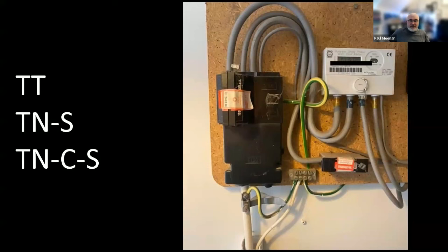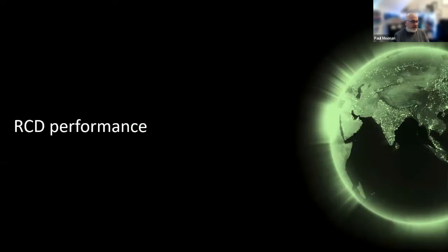We have TT, Terra Terra, which is earth electrodes, if you only have a supply live and neutral. We have TN-S, Terra Neutral Separate, so it comes in completely separate. And then TN-C-S, Terra Neutral Combined Separate, which is that cable there. It comes in from the bottom and basically connects into the fuse. But as you can see, that's a hybrid arrangement. In fact, if you look at the white cable in the earth terminal, that could go to an earth rod. So is it TT, TN-S, or TN-C-S? More than likely, it's a TN-C-S that somebody has tried to lower the impedance of by connecting to the sheath and possibly putting an electrode on, rather than fixing a network fault, because obviously, as you can imagine, cables in the ground cost a lot of money to fix and repair.